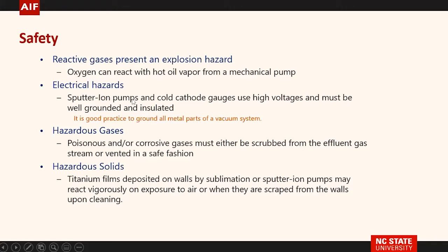Electrical. You have sputter ion pumps and gauges, some of which have high voltages on all the time. If you're working with hazardous gases, you have to be careful with that. It must be vented in a safe fashion. And I mentioned the titanium, which when it's fresh is reactive.